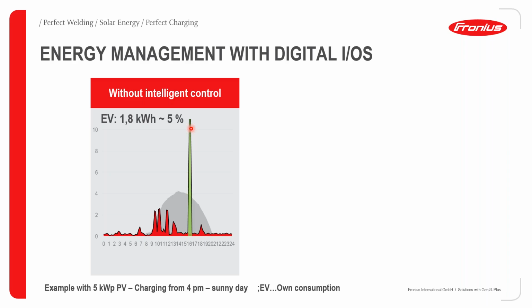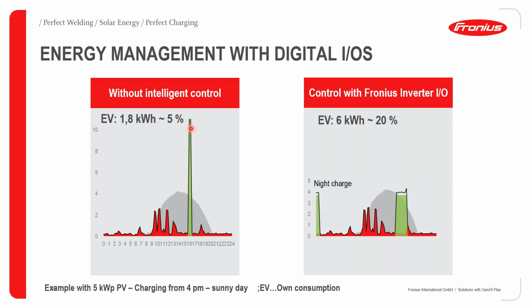In order to curb this, he can use the Fronius output ports to control his charging. By doing so, he'll be able to utilize the surplus energy generated by PV. It intelligently manages this load, and instead of taking this short period that costs more in peak period charge, he can utilize the surplus energy from his PV and charge the EV to the maximum point, but over a longer period, charging at about 3.6 kilowatts. This makes a lot of sense because he ends up not being charged for peak period usage, as compared to the case without intelligent control.